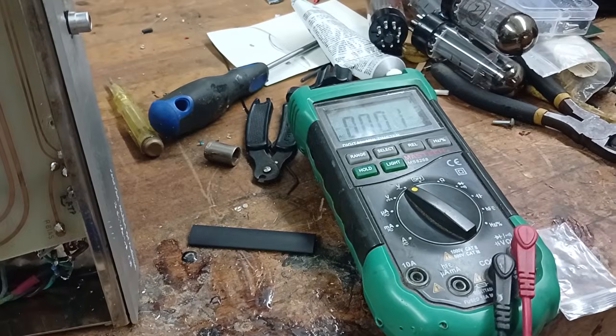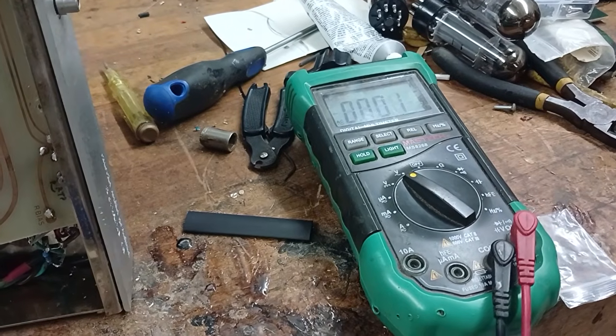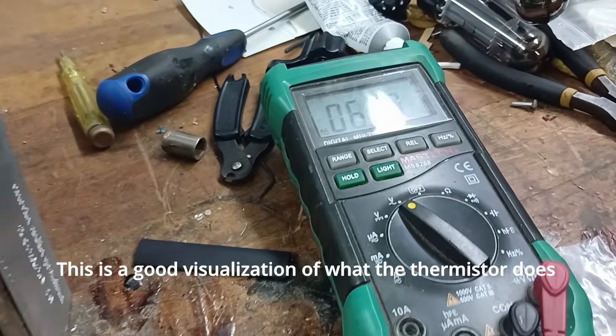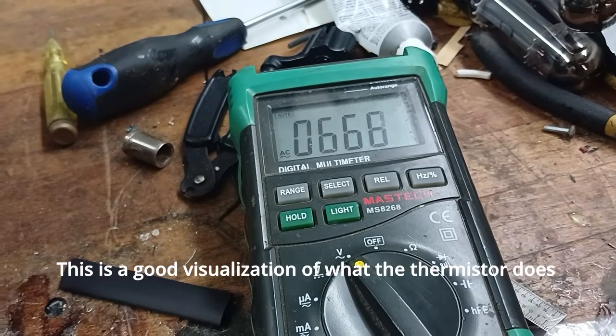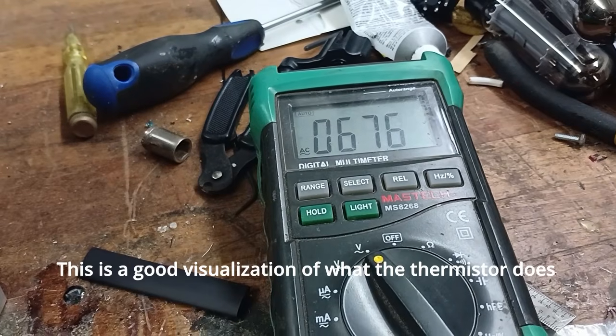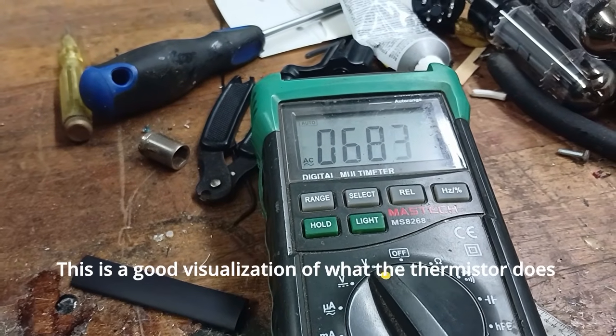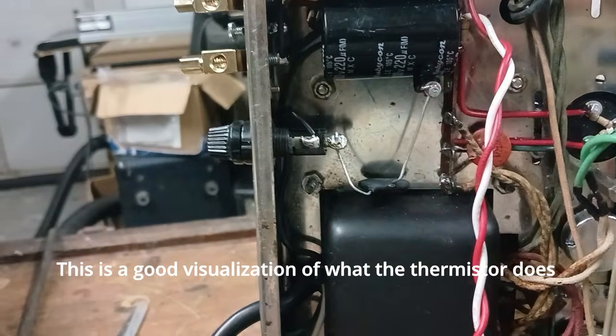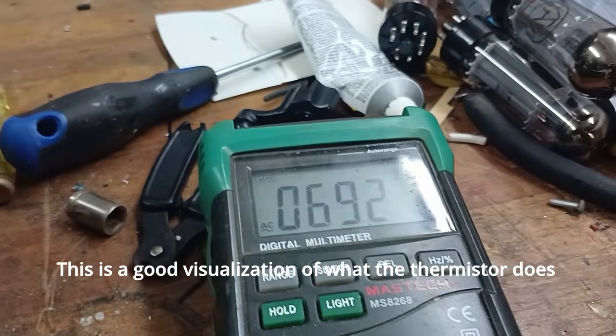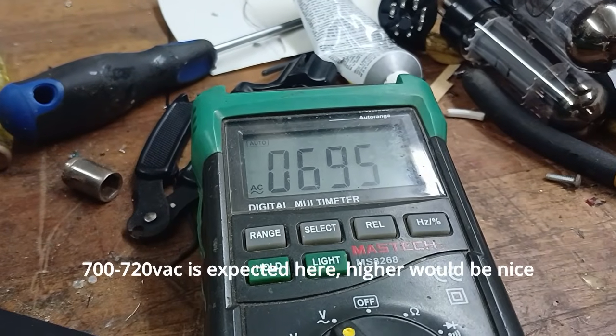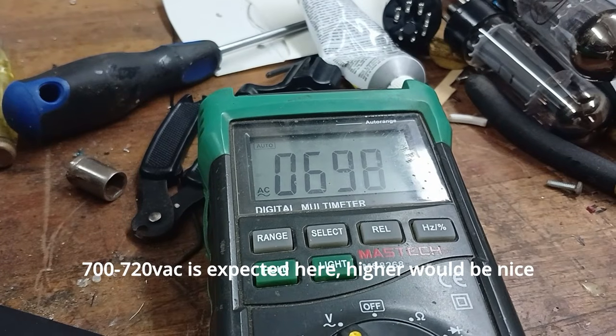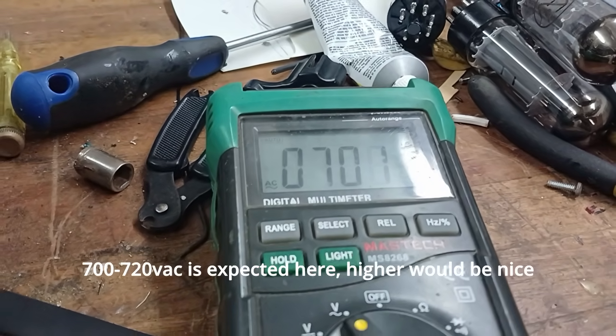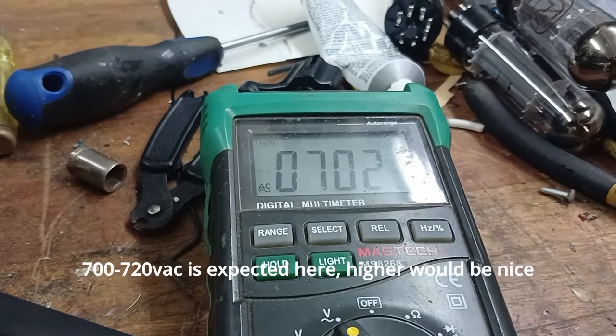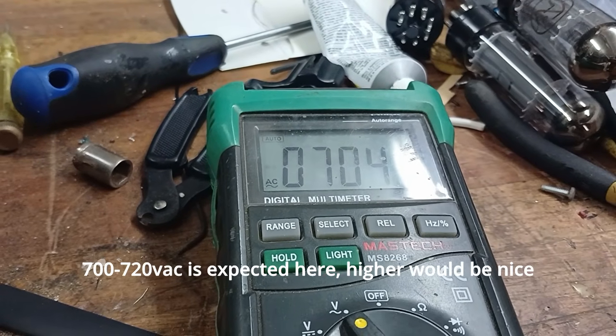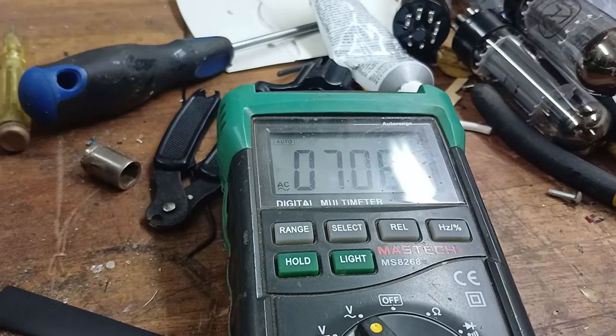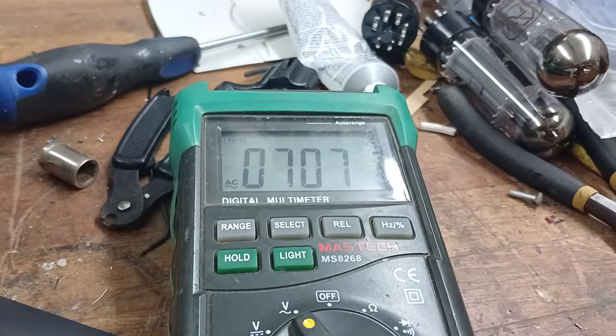Okay, I just switched it on and back off, but I did notice a slow ramp up in voltage—it hung out at 500 volts for a second, and then ramped up. That's exactly what the thermistor is doing: as it heats up, it's lowering its resistance, and this is increasing. We want 700, and I think we can agree we're getting 700. So as far as specs go, this transformer is doing what it's supposed to be doing.